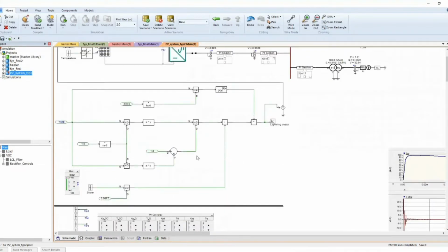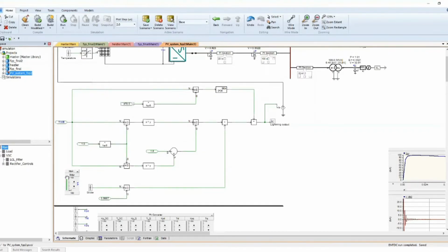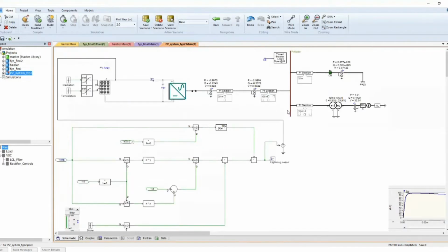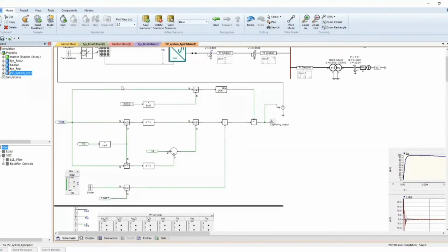In order to generate lightning impulse, here is the circuit that has been referred to the Heidler function. Here, this input is for the rise time constant, and this input is for the decay time constant. This slider is used to set the peak current. This is the peak of lightning current. So the function of the circuit will go as the lightning output, and the lightning output will be a current source that will go into the positive side of the DC of the PV photovoltaic source.